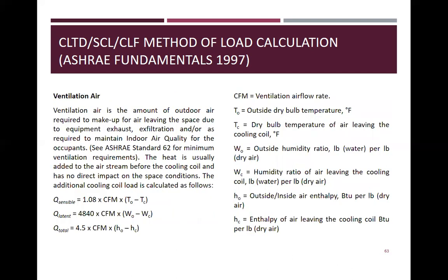Ventilation air. Ventilation air is the amount of outside air required to make up for air leaving the space due to equipment exhaust, exfiltration, and or as required to maintain indoor air quality. See ASHRAE Standard 62 for minimum ventilation air requirement. The heat is usually added to the airstream before the cooling coil and has no direct impact on the space condition. The additional cooling coil load is calculated as follows.